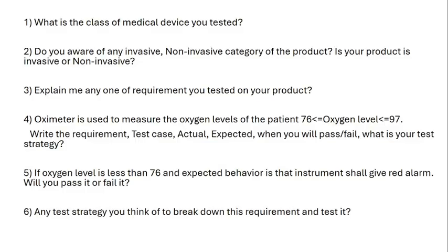Okay. So the first question is, what is the class of medical device you tested? If you see, there are three classes of medical devices. In class one the risk is low, if the risk is medium then it is class two, and if the risk is high then it is class three. I worked on an electrosurgical generator, so I said it is a class two device where the risk is medium.